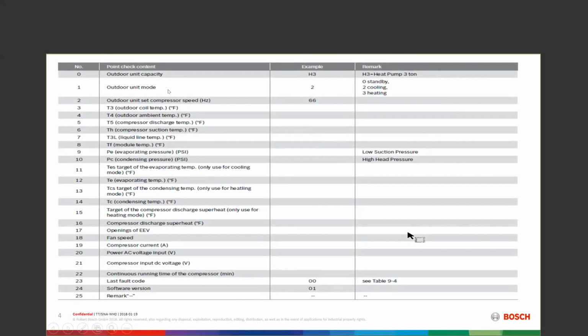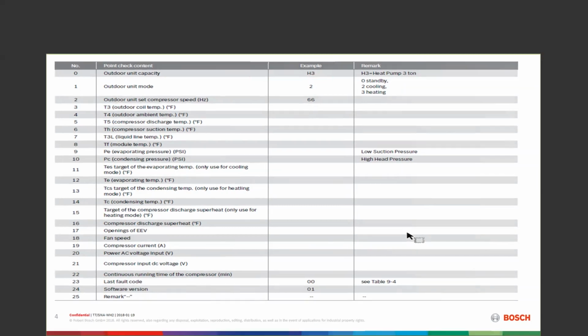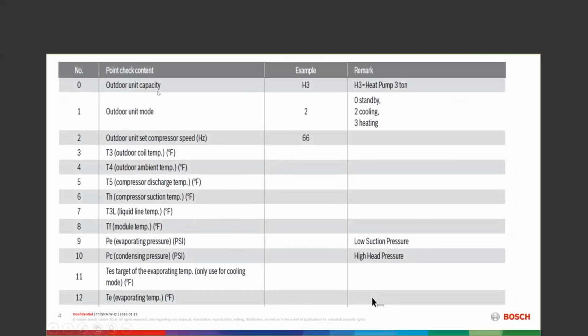When I get a 0-1, that is going to be my call coming from my thermostat. It may be 0. I may not have a call. That thermostat may be in a time delay at this point in time, but it's going to show me what I am getting in that particular scenario. So it's a 0 or it's a 2 in cooling, it's a 3 in heating. There are my parameters. Very, very nice, very good logic to show you what's going on. Whoops, I did not mean to do that. Let's go back.